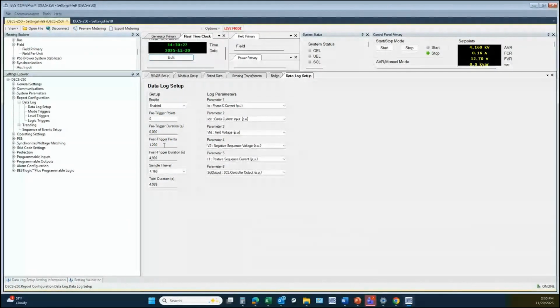If what you're trying to capture a data log on is a start, then obviously you don't really need too many data points recorded before the start. But if you're trying to record on a event like your breaker tripped open, or a loss of excitation condition, or an overexcitation limiter, then you would really need to see what was happening right before the event occurred. By default, there are no pre-triggered points, but we have a total of 1,200 points available. So I'm going to set that to 600.